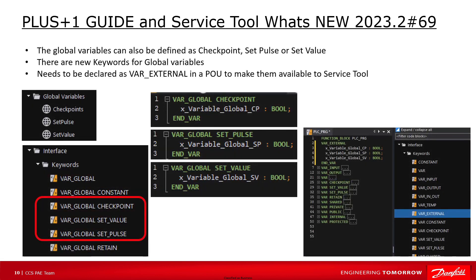Global variables can also be defined as checkpoint, set pulse, or set value via the new sections var global checkpoint, var global set value, and var global set pulse. For each keyword a separate global variable list needs to be created to declare the variables. After declaring them under global variables, you also have to declare them as var external in a POU to make them available to the Service Tool.